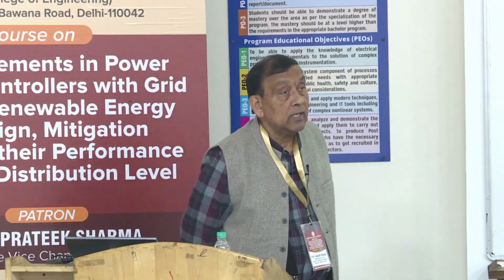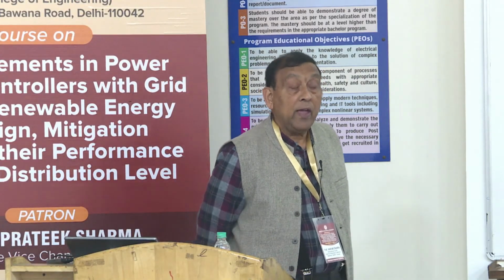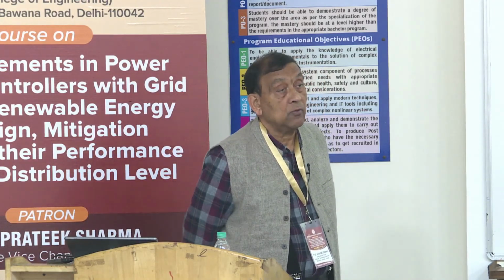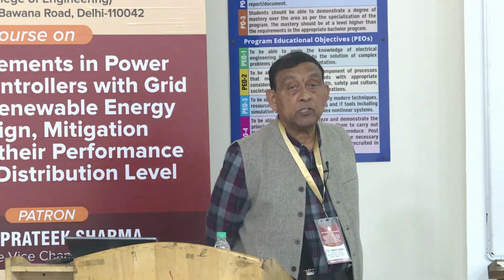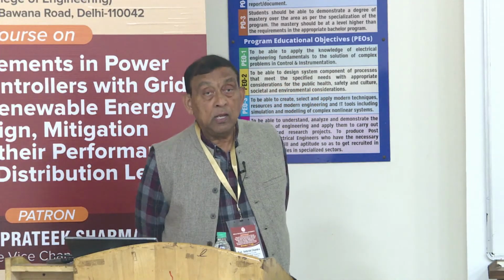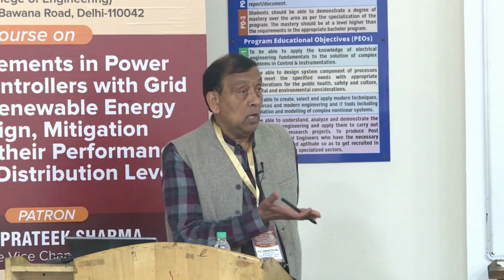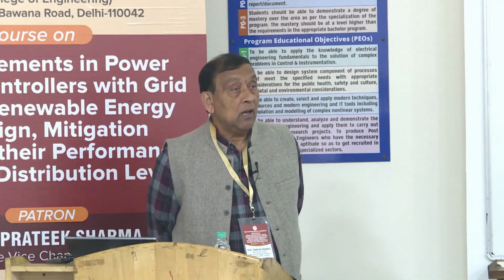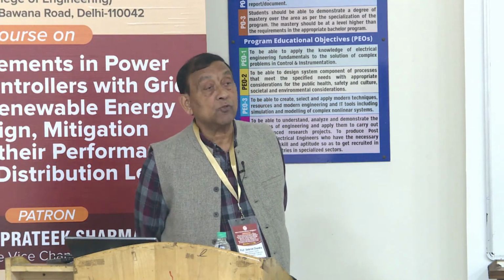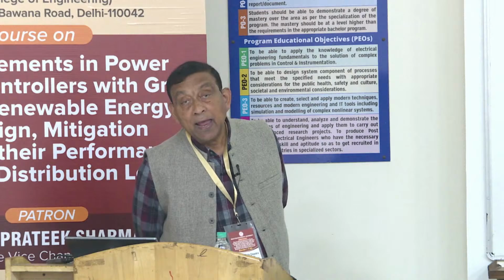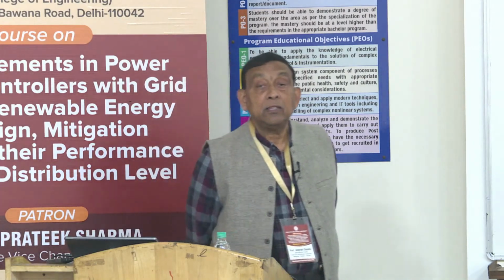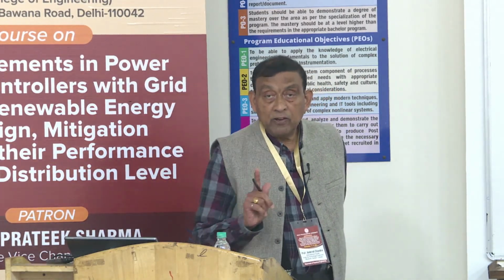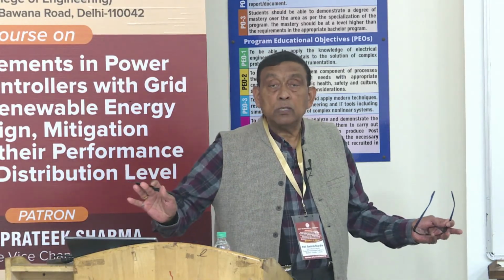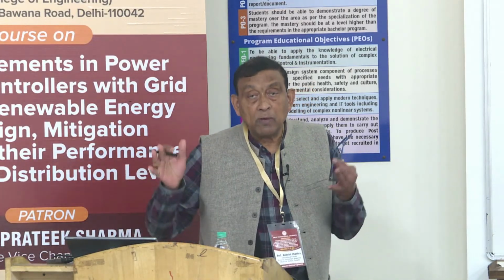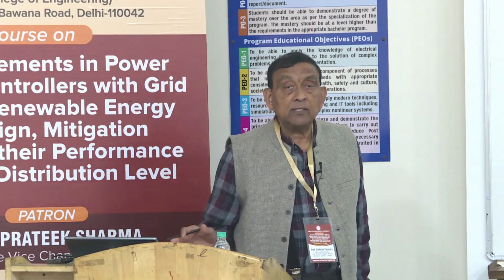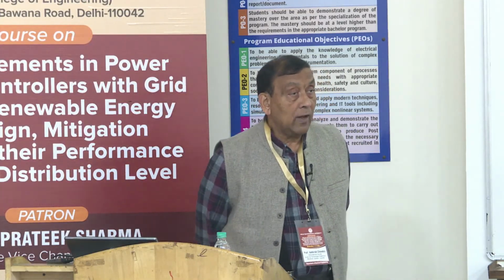And if you have this kind of transformer, it is very difficult to transport it. You need special means to transport that transformer. So this is a big advantage. Although the efficiency is high, a single 3-phase transformer has higher efficiency than 3 single phase.